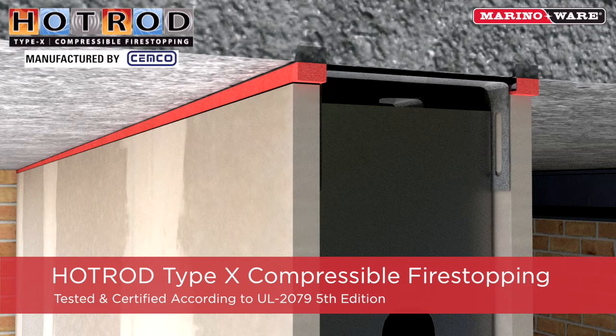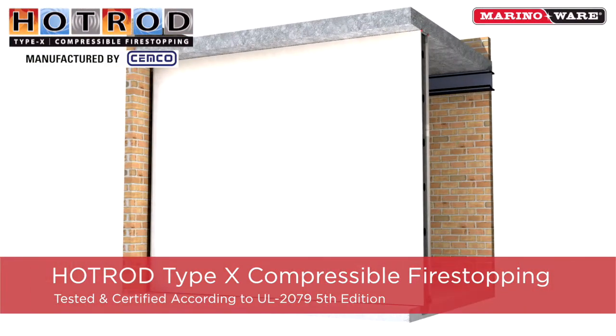The red-colored hot rod is easily identified by the inspector, and once the inspection is complete, the hot rod can either remain exposed, or be concealed by a drop ceiling, or covered with a flat vinyl deflection bead or flat tape and joint compound.